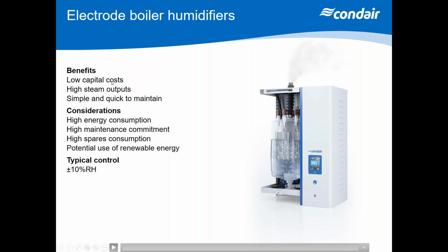Now, they are pound for pound the cheapest form of humidifier out there. And you can get high steam outputs out of them. They start at 5 and they go up to 160 kilos an hour in 4 boiling chambers. And they're simple and quick to maintain. Just got to drain them down and change the cylinder. You need to clean them out as well. But typically they're a really good unit.